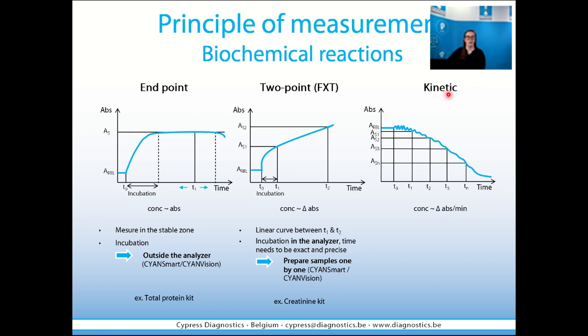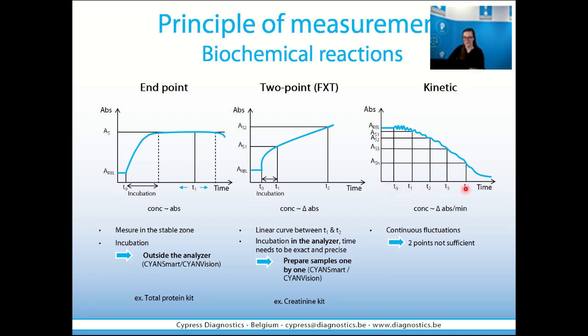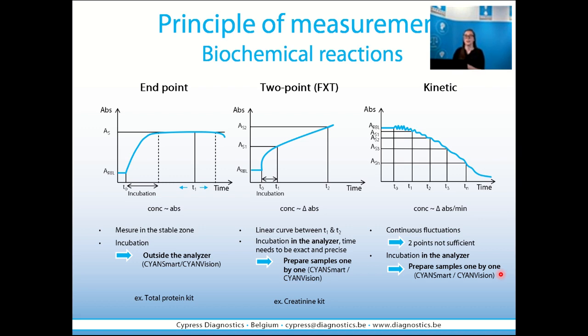The third type of biochemical reaction is the kinetic ones. Kinetic reactions are characterized by continuous fluctuations in absorbance. You need to measure at different time points — it is not enough to measure the absorbance of your mixture only at two points. This also means that the incubation needs to take place inside the analyzer and you need to prepare samples one by one. For example, this is true for our GOT and GPT kits.